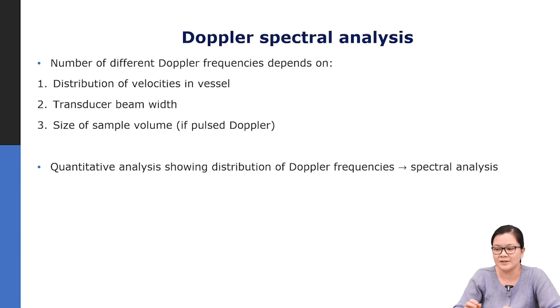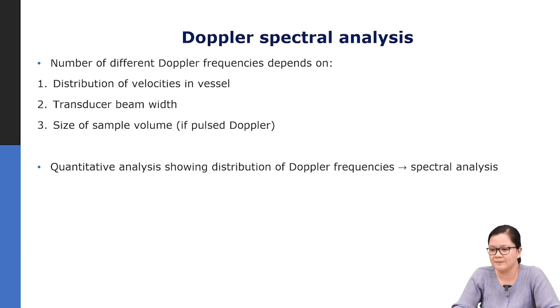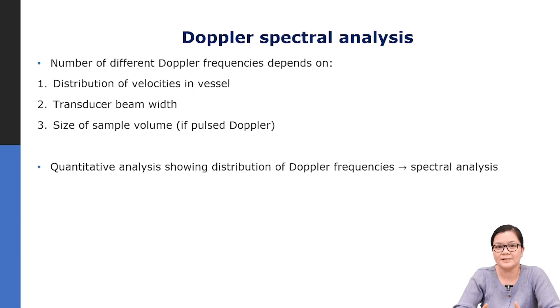The number of different Doppler frequencies depends on the distribution of velocities in the vessel. Laminar flow produces a narrow velocity distribution; turbulent flow produces a much wider distribution with scatterers moving in various directions and speeds. The transducer beam width also matters: a smaller beam width interrogates a smaller vessel region with a narrower velocity profile. The sample volume size is also important, especially for pulsed Doppler. This velocity distribution is analyzed through Doppler spectral analysis — a quantitative analysis showing the distribution of Doppler frequencies.